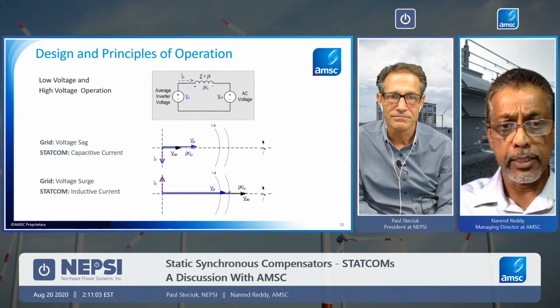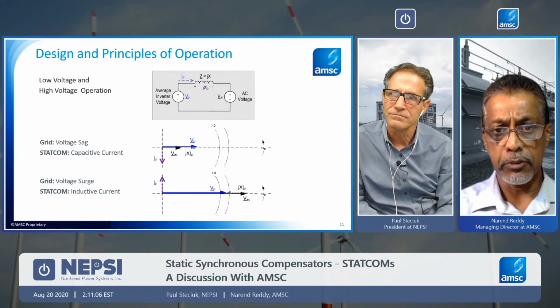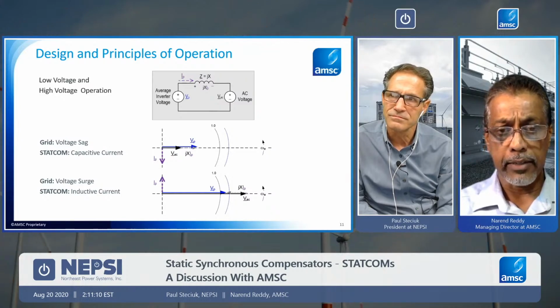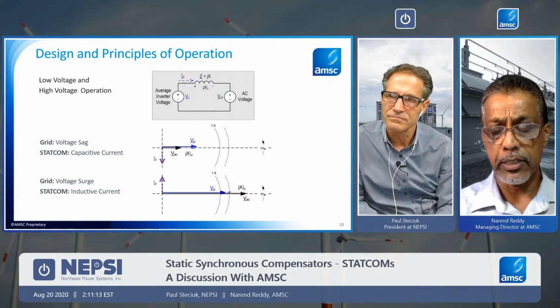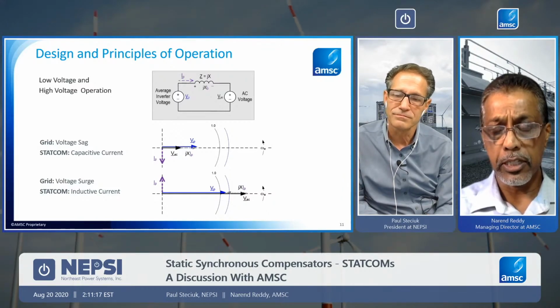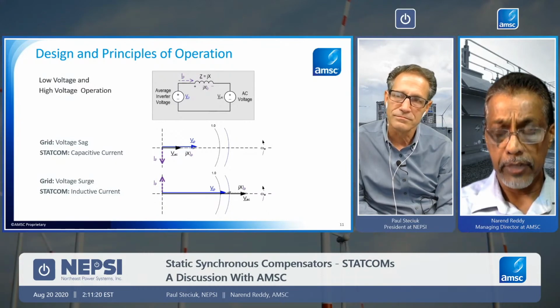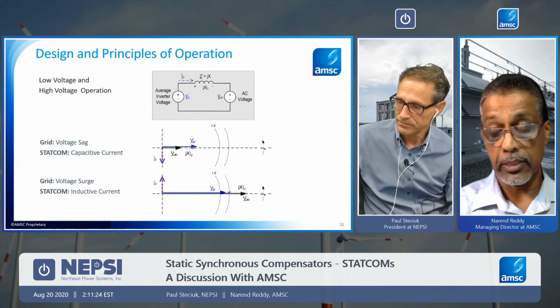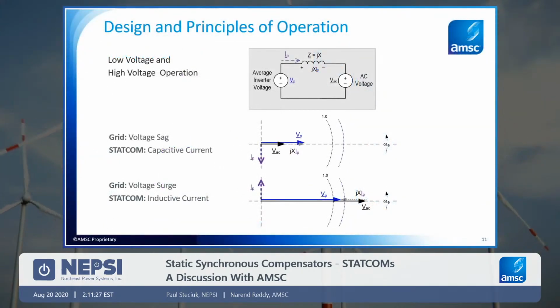The control system can dictate exactly how much current is needed and whether it's capacitive or inductive. So really, when there is a low voltage operation, the inverter is looking at a capacitive function. The inverter voltage would be considered higher than the AC system voltage, and the inverter current is pushed out through an impedance, which is usually the transformer impedance, as well as some internal impedances of the inverter system. In an inductive current requirement, if the grid voltage is higher than nominal, the STATCOM will inject current 90 degrees lagging to the voltage, and that has the effect of reducing the system voltage at the connection point, similar to how a capacitor or a reactor would in each of these situations.